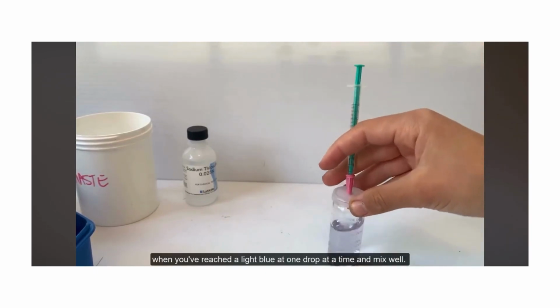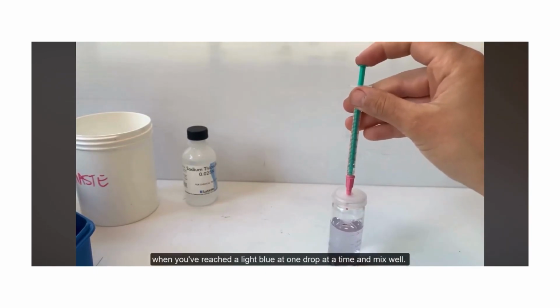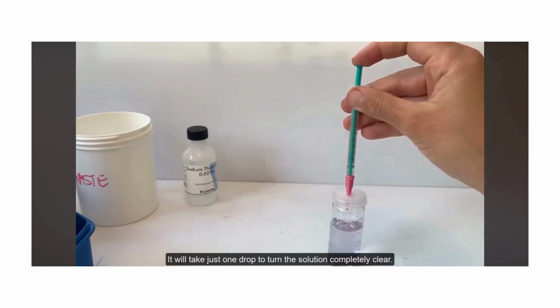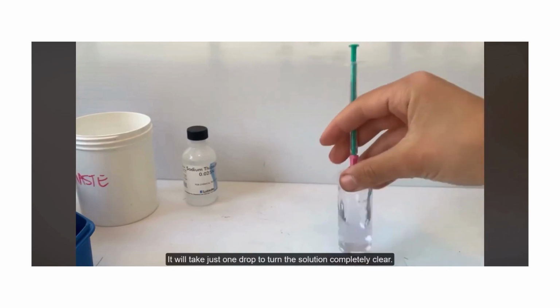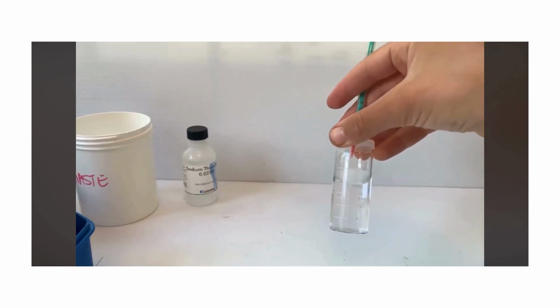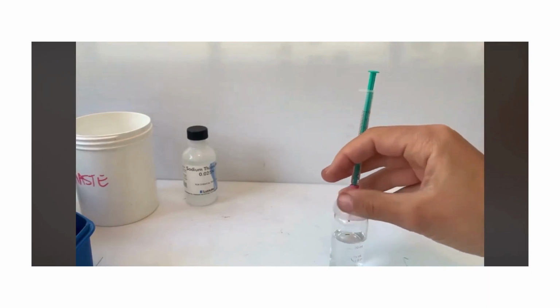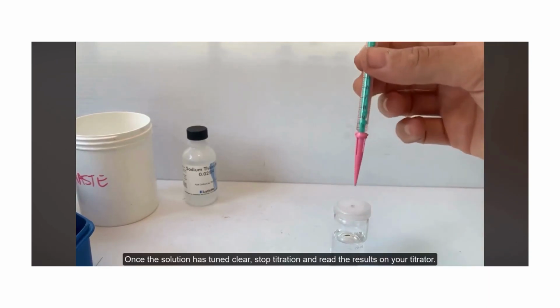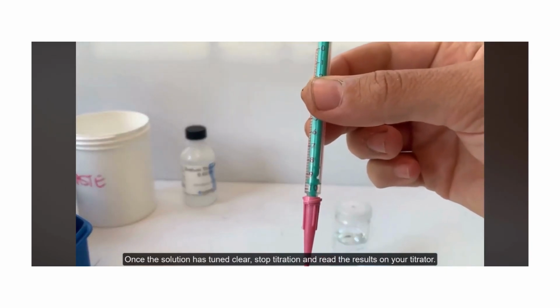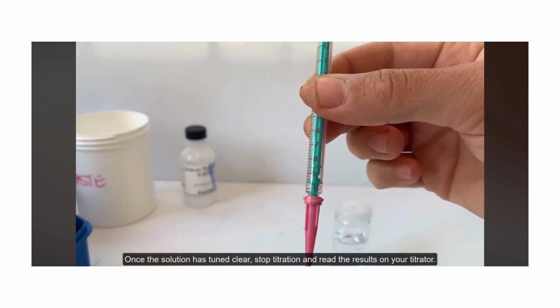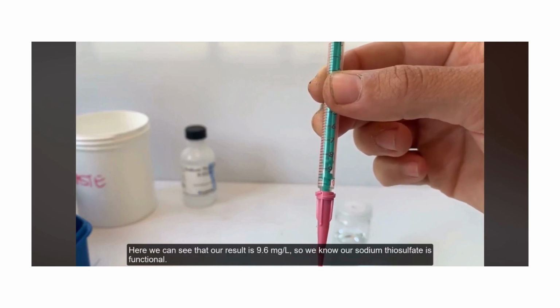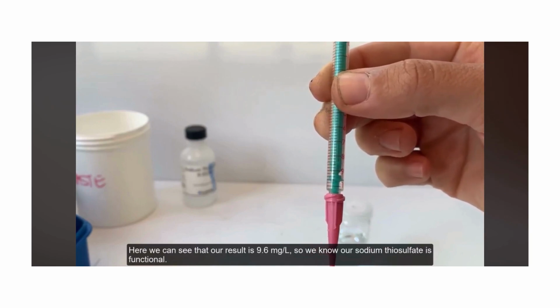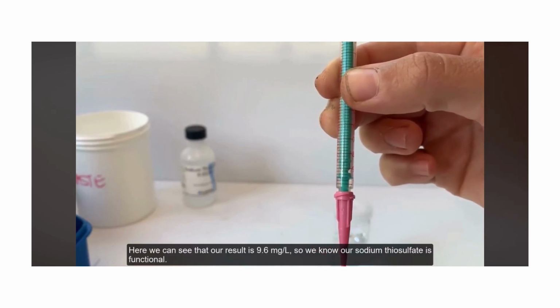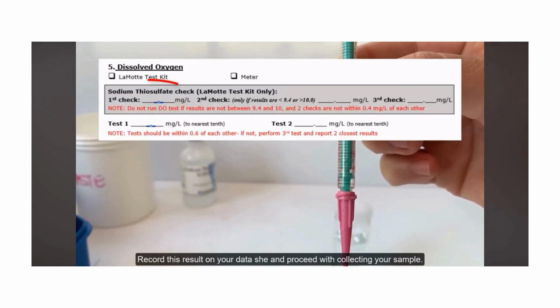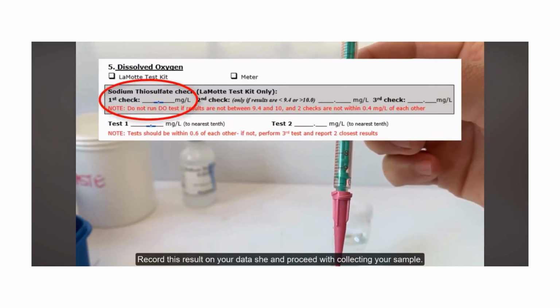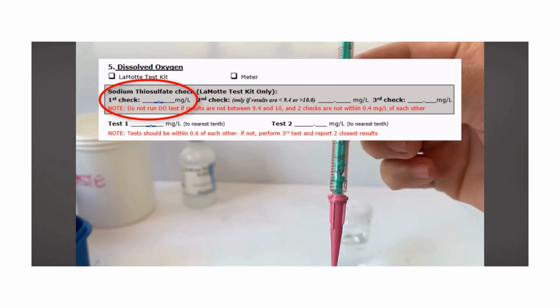When you have reached light blue, add 1 drop at a time and mix well. It will take just 1 drop to turn the solution completely clear. Once the solution has turned clear, stop titration and read the results on your titrator. Here we can see that our result is 9.6 milligrams per liter, so we know our sodium thiosulfate is functional. Record this result on your datasheet and proceed with collecting your sample.